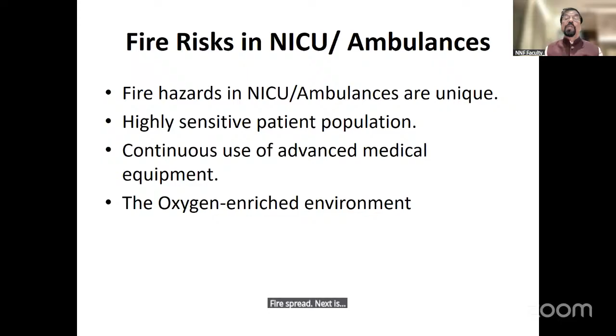Next is high electrical load, another major contributor to fire risk in an ICU. We run multiple devices - incubator, warmer, monitor, infusion pump - simultaneously 24/7. Problems arise when multiple devices run on one extension board, old wiring is not replaced regularly, plugs get overheated, and equipment maintenance is skipped. Regular electrical audits, proper load distribution, and avoiding extensions are very critical for fire safety.